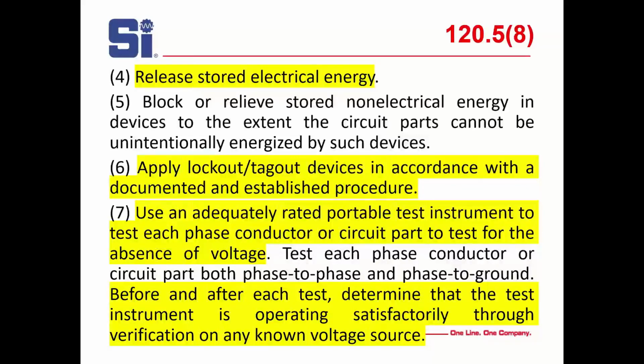Use an adequately rated portable test instrument to test each phase conductor or circuit part for the absence of voltage. And then you test them phase to phase and phase to ground. Before and after each test, determine that the test instrument is operating satisfactorily. So you want to go back and do a test on a known live object, circuit, whatever. Test your grounding, and then retest the equipment.